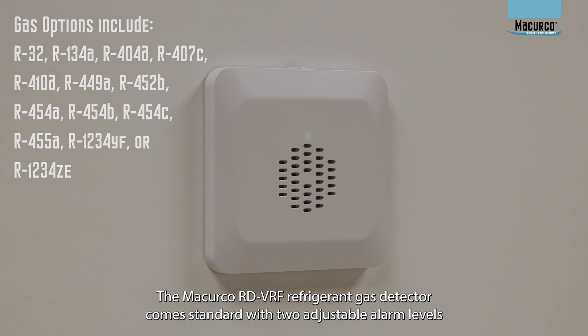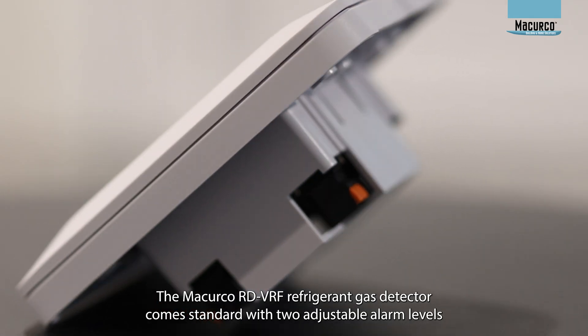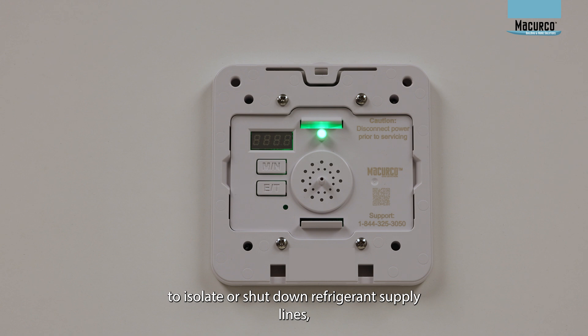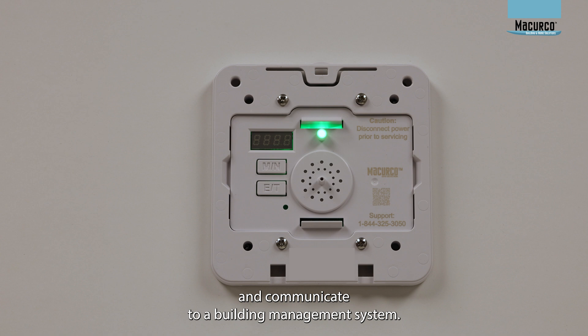The Macurco RD-VRF Refrigerant Gas Detector comes standard with two adjustable alarm levels to activate two onboard relays that can be used to control valves to isolate or shut down refrigerant supply lines, engage exhaust fans, provide notification alarms, and communicate to a building management system.